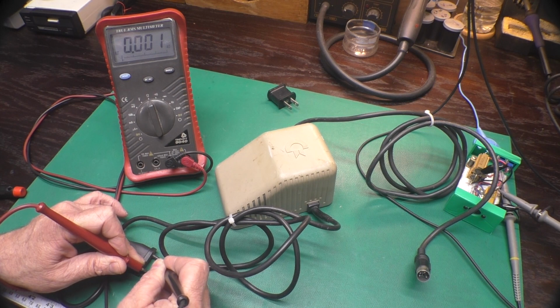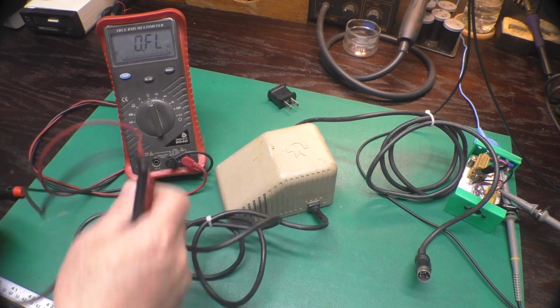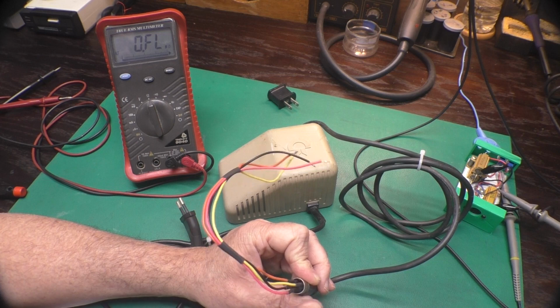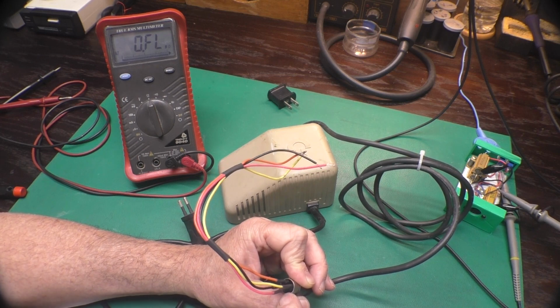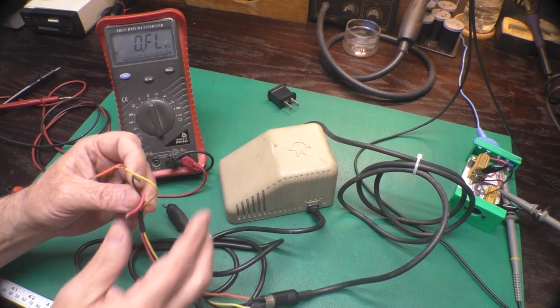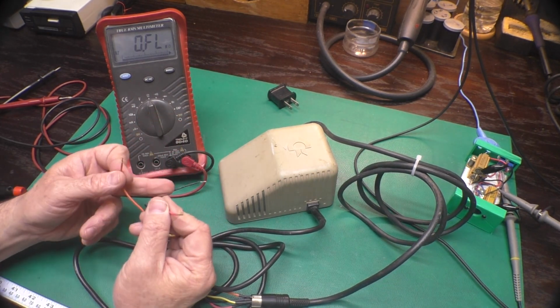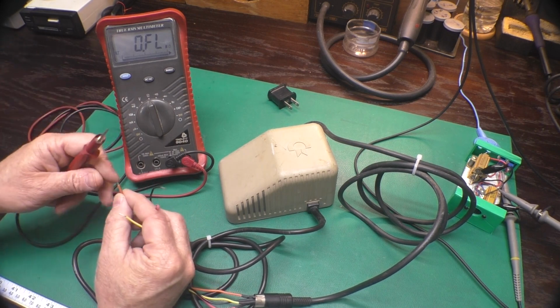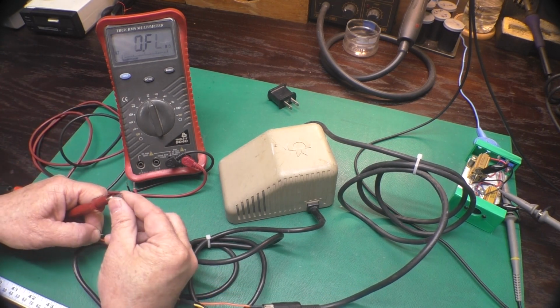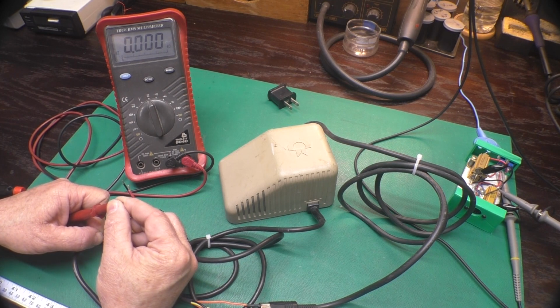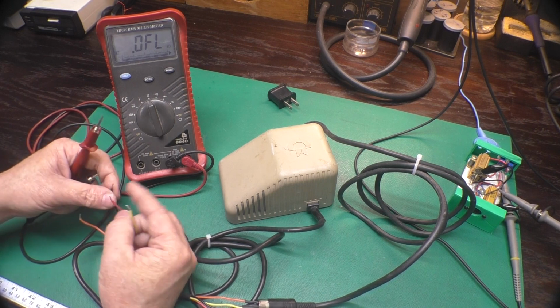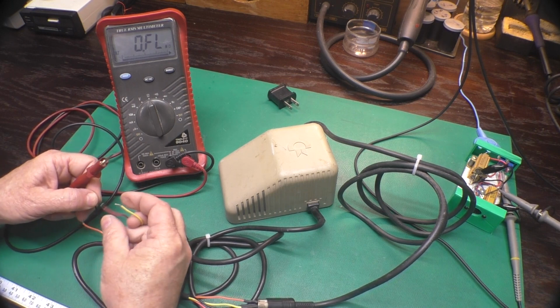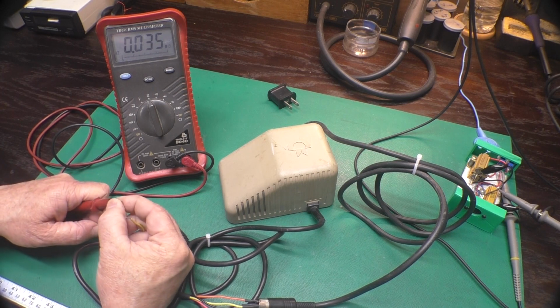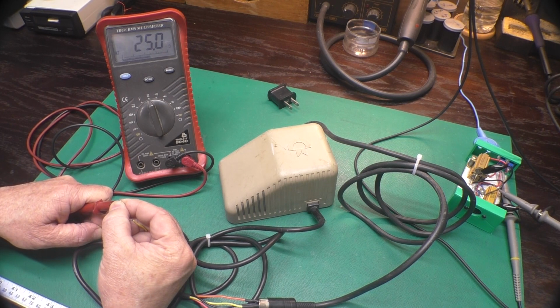Now we'll move on to our Wedge power supply, and we'll ohm out the AC input, and we have about 17 ohms, which is fine. When setting up to ohm out the AC and DC outputs, I noticed the DC output pins are in a slightly different position, so I'm not sure if this will work with my load tester or not. We'll have to see how that goes. On the AC output side, we have less than an ohm, but that's fine, it's not a direct short, it just depends on the transformer winding. Then we'll check the DC output, and we have about 250 ohms, which is fine.